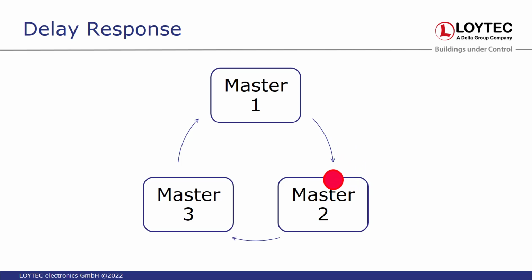If one device does not respond, the token gets lost. The device tries to give the token to the next device, sees that the token is not passed on, so it tries again, and after, I don't know, 3 retries, somebody needs to regenerate the token because the token is just lost on the network, it's dropped. And this, of course, slows down the whole communication.